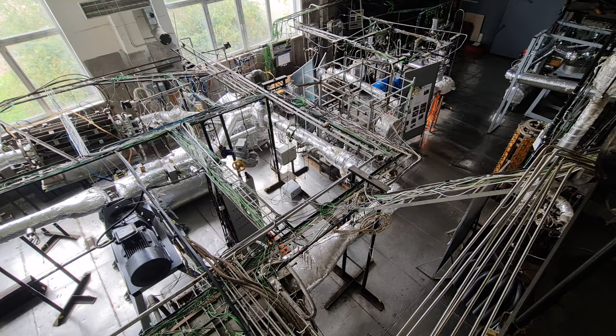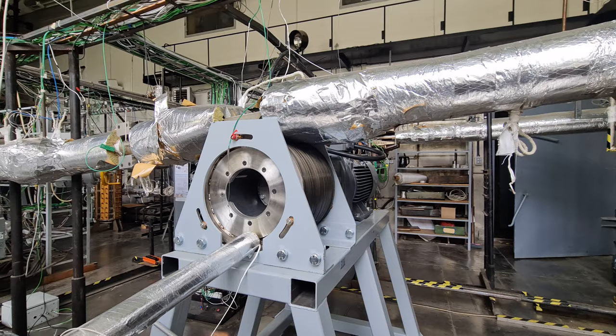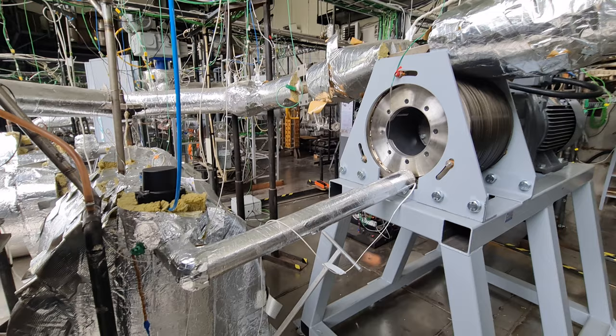In this shot you see a permanent magnet pump, which can produce up to 20 bar pressure or 50 liters per second flow rate of sodium. In such circuits, we test and measure characteristics like pressure and flow rate curves that characterize the performance of the developed pumps.